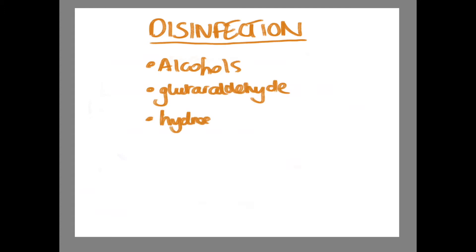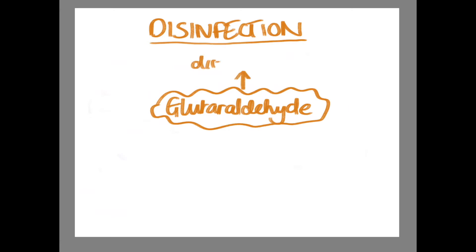Disinfection: Disinfectants are generally unable to remove microbiological spores. However, there are some higher level disinfectants, such as glutaraldehyde, that if left long enough will produce sterility. Disinfectants include alcohols, glutaraldehyde, and hydrogen peroxide. Glutaraldehyde is generally used for disinfecting endoscopes.